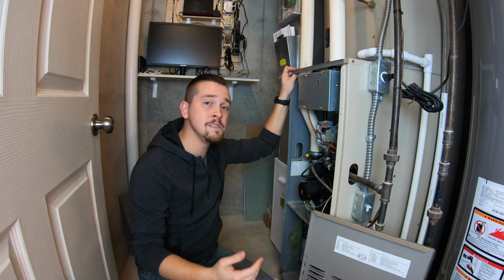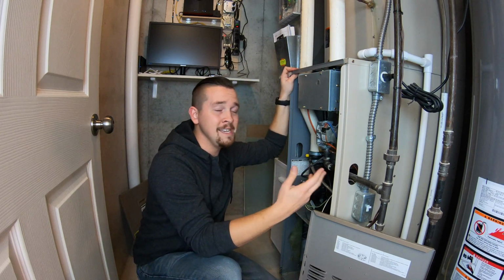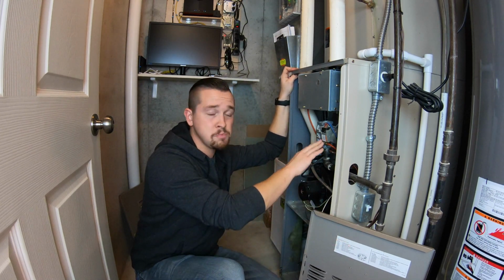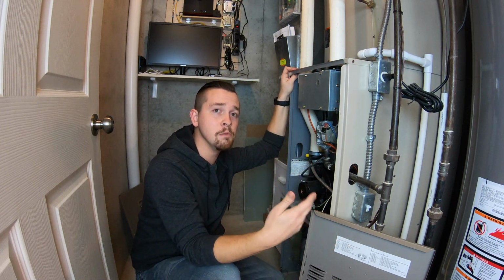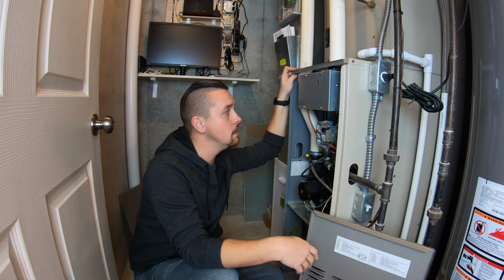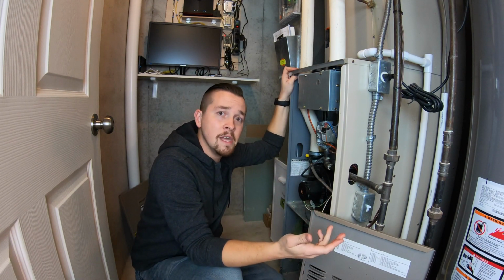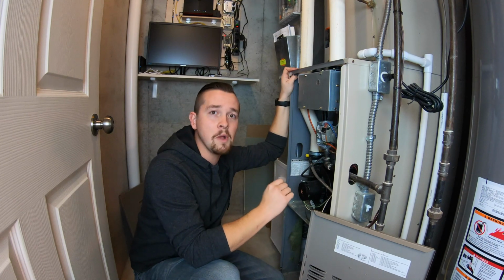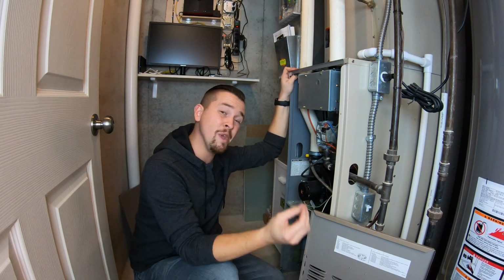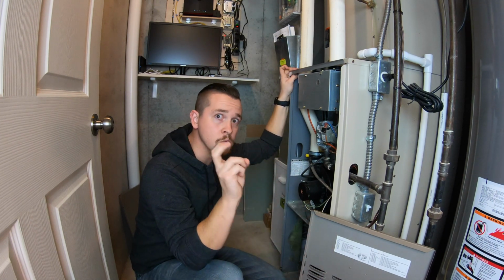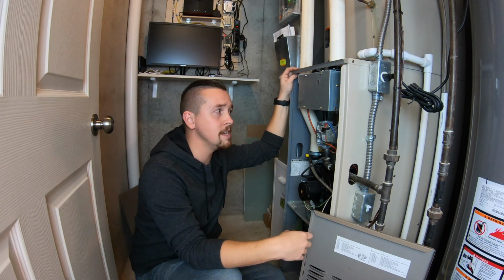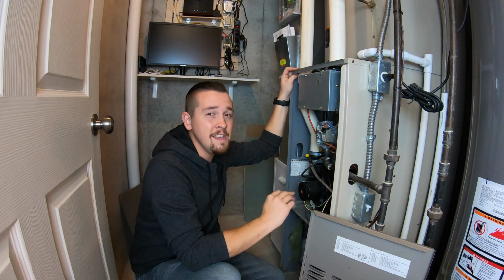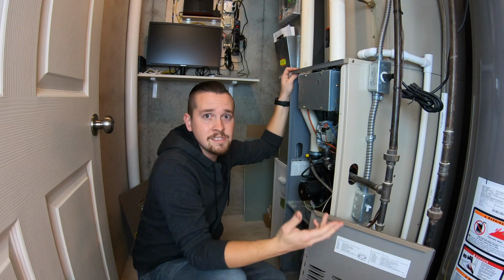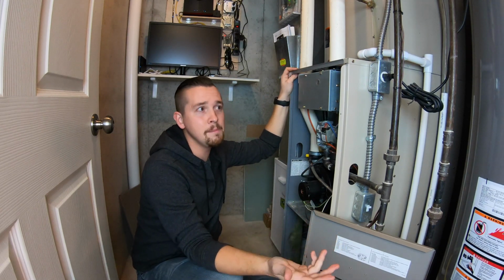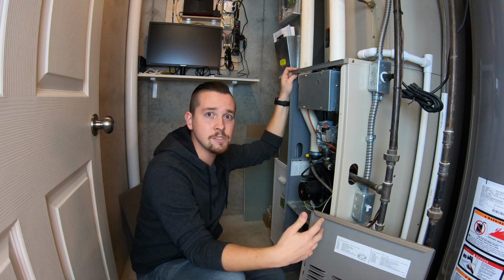And again, those tend to break when they aren't maintained, if the burners aren't clean or if the gas pressures aren't set properly. You'll kind of blow through igniters a little bit quickly. There's certain igniters out there that are less likely to break, although I generally recommend replacing your igniter with the OEM igniter, not a universal replacement. A lot of times the universal replacement, even though it says it works, it says it fits and technically does, I end up having more problems than success with.